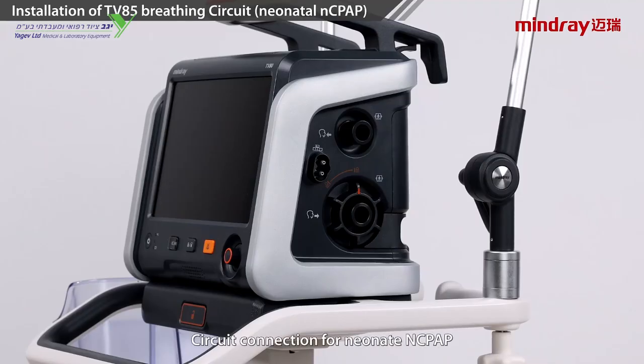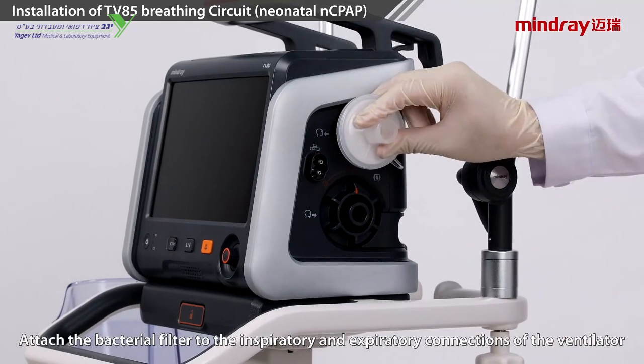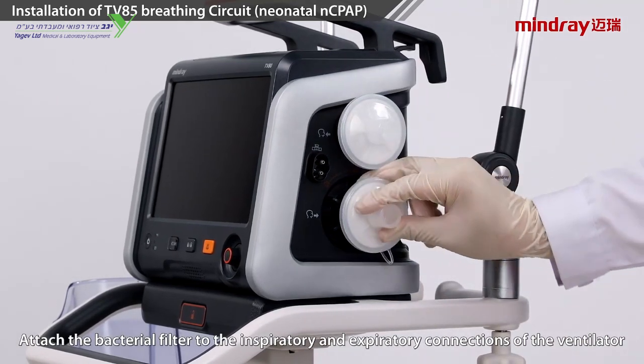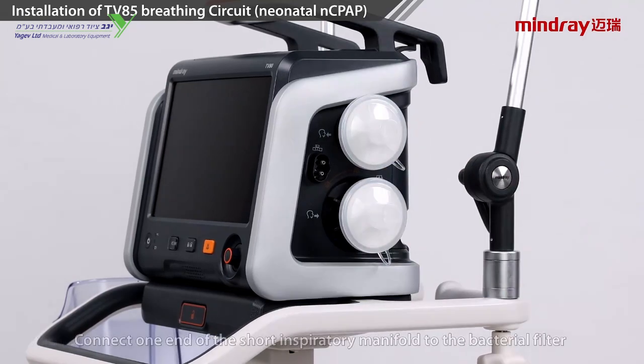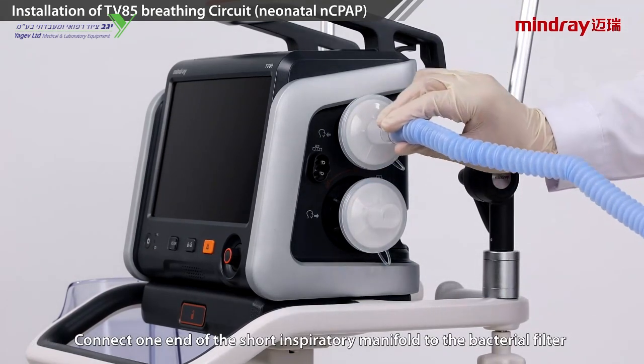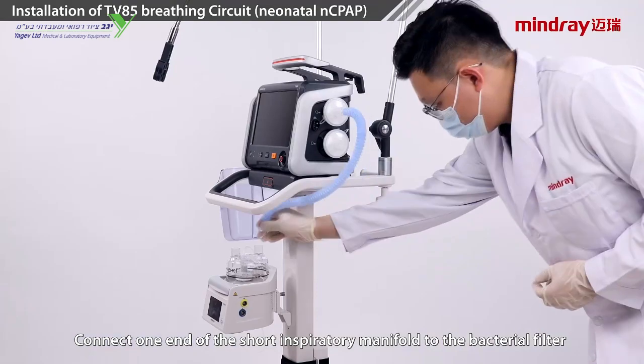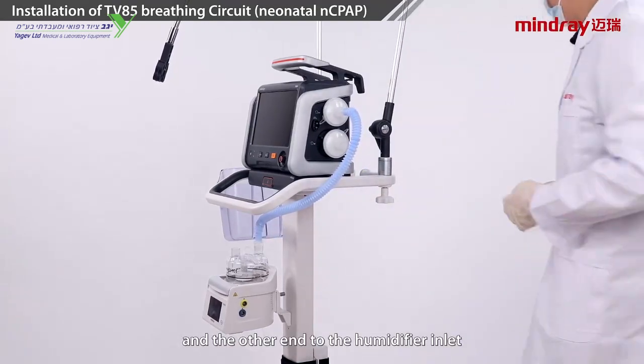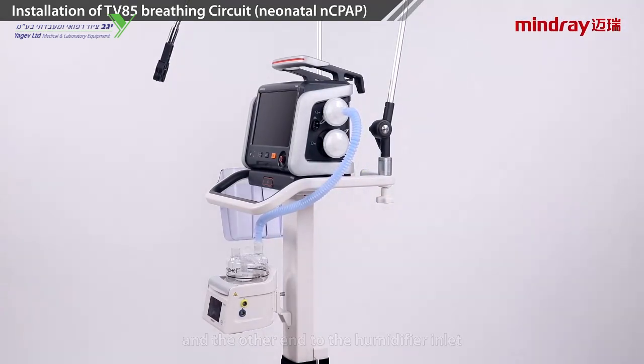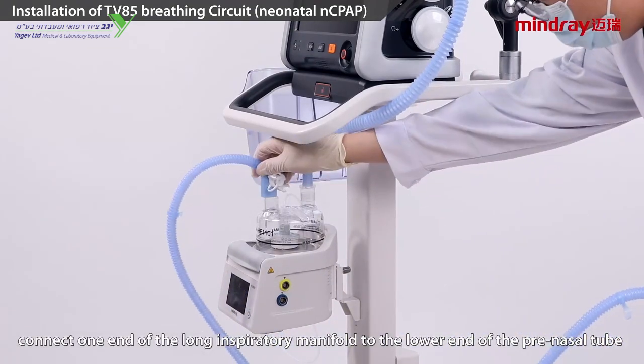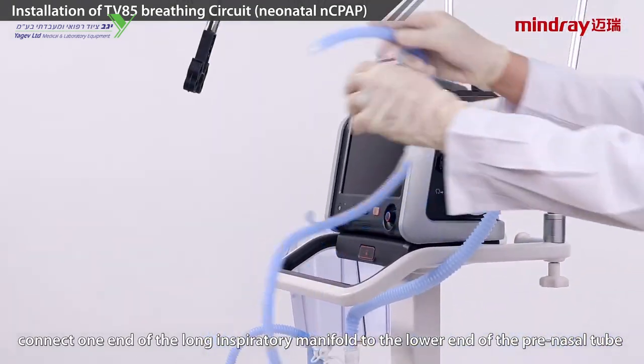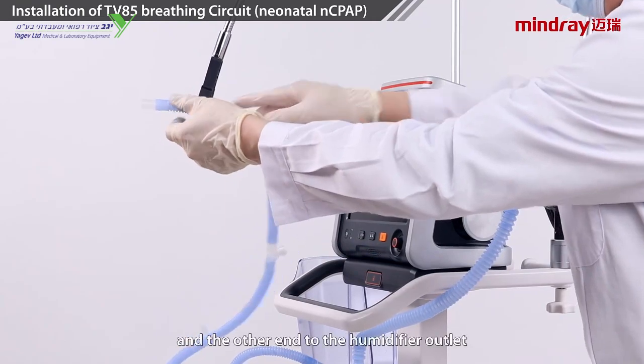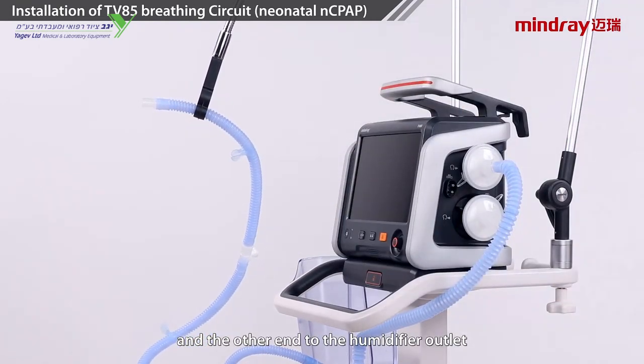Circuit connection for neonatal nCPAP. Attach the bacterial filter to the inspiratory and expiratory connections of the ventilator. Connect one end of the short inspiratory manifold to the bacterial filter and the other end to the humidifier inlet. Connect one end of the long inspiratory manifold to the lower end of the prenasal tube and the other end to the humidifier outlet.